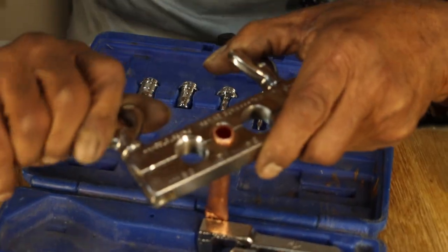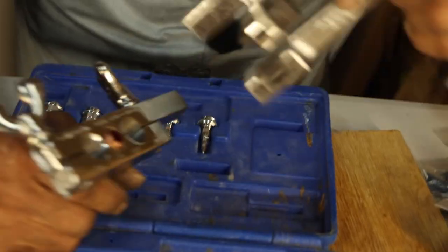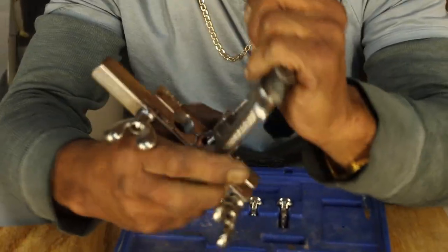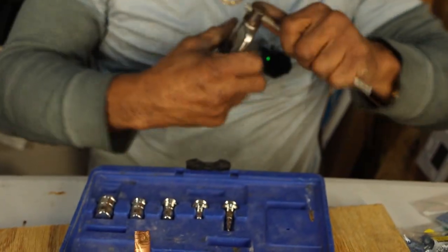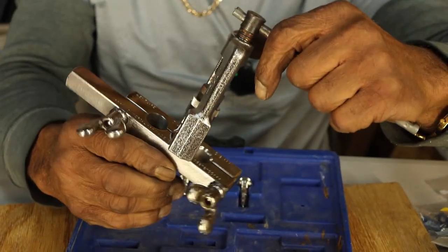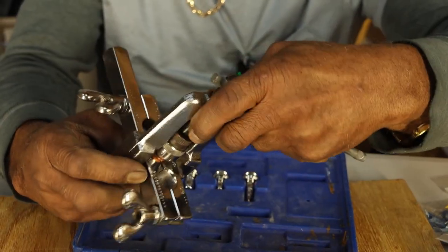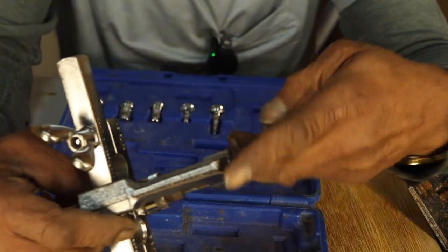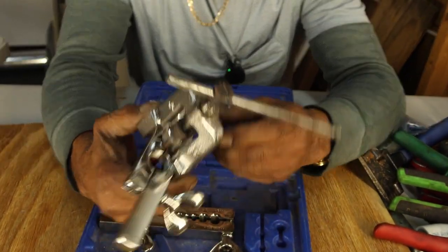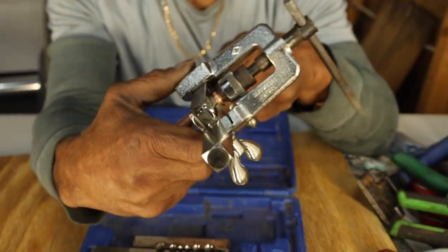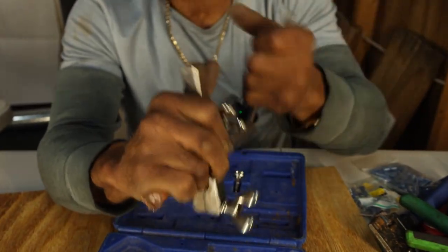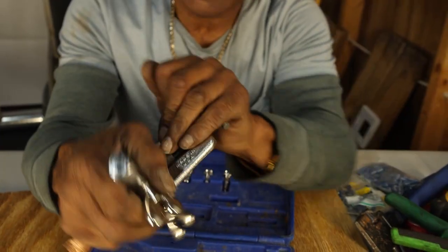Now, once I tighten that in, I can then take this, hook it on. I need to loosen it up a little bit, back it up, so that, why is it so tight? It should never be that tight. But I can hook this on, and it's still got to loosen up some. And as I go down in it, I can get it down far enough to get my connection made where I'm connected on the copper with my nose going into the copper. Now, as I tighten this, it's going to flare that copper. And that is used in what we call flare nut connections, okay?